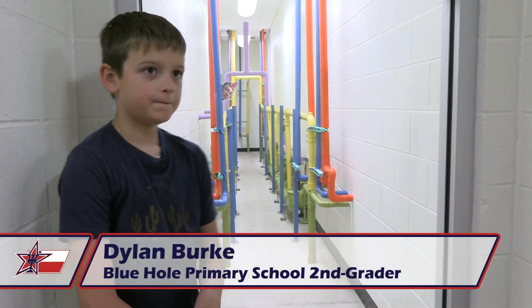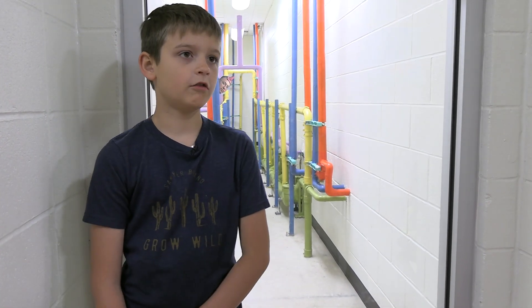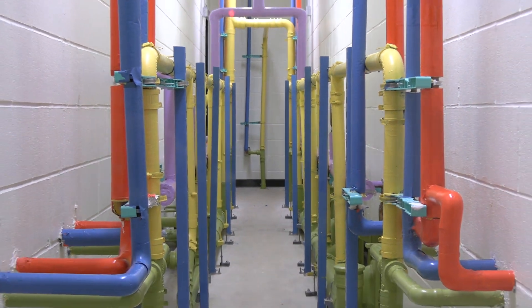This is the plumbing window. All the pipes are color coded to what they mean. Red is hot and potable water. Blue is cold and also potable water. Both are from Aqua Texas groundwater. Yellow means ventilation. Green is gray water, also called dirty water. Purple is rainwater and AC condensate, also known as site harvested water.